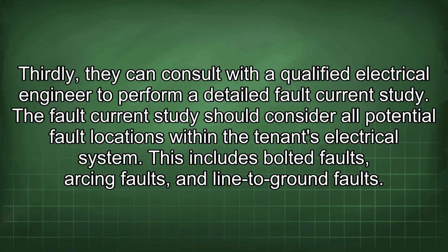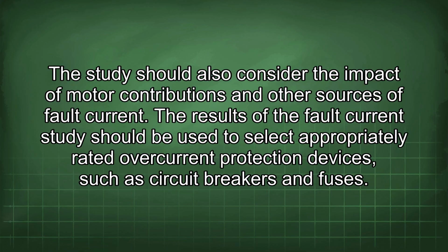The fault current study should consider all potential fault locations within the tenant's electrical system. This includes bolted faults, arcing faults, and line-to-ground faults. The study should also consider the impact of motor contributions and other sources of fault current.